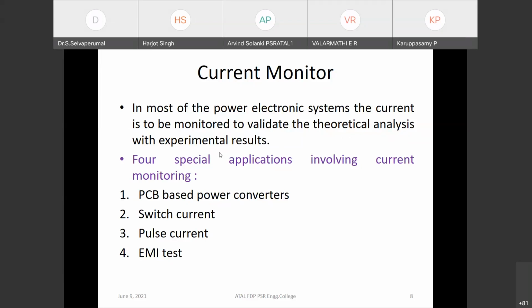Hall effect current sensors are widely used to monitor currents in electric motors and power converters. Typical bandwidth of these sensors is 200 kilohertz, sufficient to capture DC to AC current along with switching ripples. In resonant converters, the fundamental frequency of the current may go as high as 1 megahertz, and current transformers find frequent use in these converters. Four special applications involving current monitoring include PCB based power converters, switch current, pulse current, and EMI test.